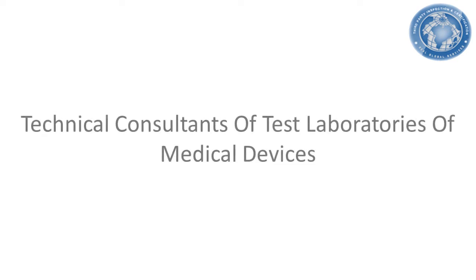Our team has people who have worked on protocol development and accreditation as per ISO 17025 of laboratories which test medical devices as per the EN 60601 series of standards for general electrical safety, EMI/EMC, and different particular standards, including biocompatibility, sterility, and stability testing by method of real-time study and accelerated aging study.